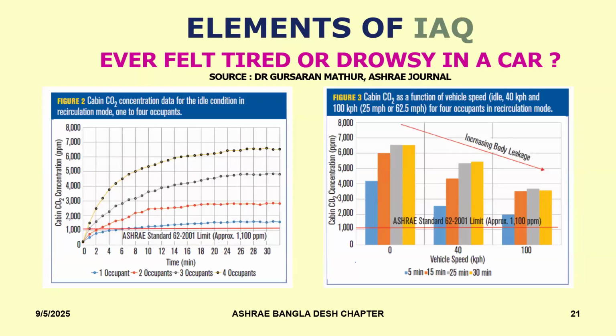I actually got this article which appeared in the January 2025 issue of our ASHRAE Journal, where Dr. Gursaran Mathur has written an excellent article on cabin CO2 in automobiles. Now, if you see this chart on the left-hand side, you can see how the CO2 concentration builds up in an automobile. You see those four lines, the blue line and the orange line, and that represents the number of people in the car. So if you have 4 occupants and you start driving off, within about 20 minutes, the CO2 level would have reached about 6,000 ppm.